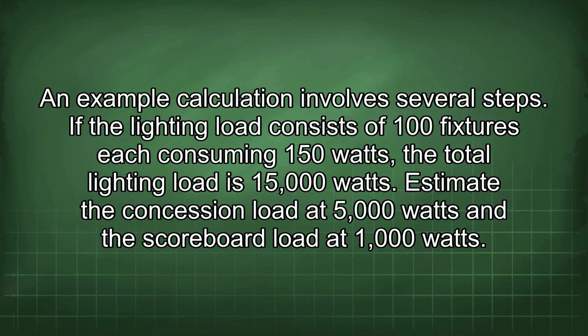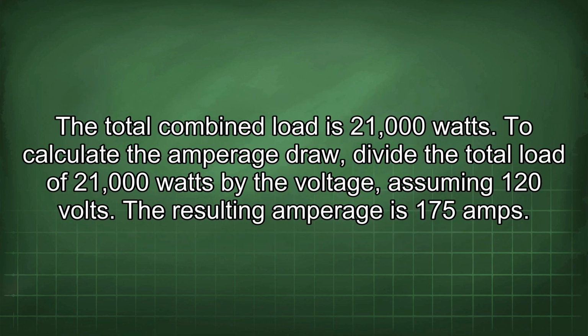An example calculation involves several steps. If the lighting load consists of 100 fixtures each consuming 150 watts, the total lighting load is 15,000 watts. Estimate the concession load at 5,000 watts and the scoreboard load at 1,000 watts. The total combined load is 21,000 watts. To calculate the amperage draw, divide the total load of 21,000 watts by the voltage, assuming 120 volts. The resulting amperage is 175 amps.